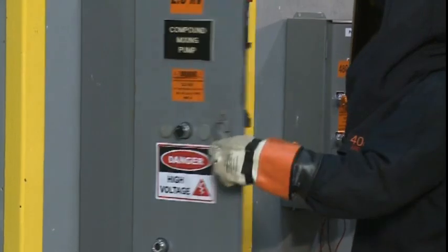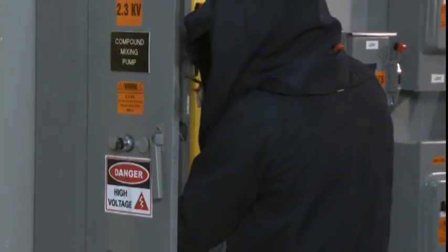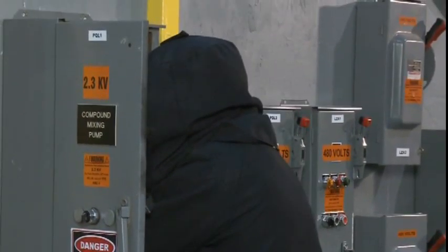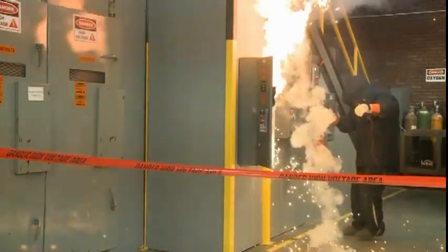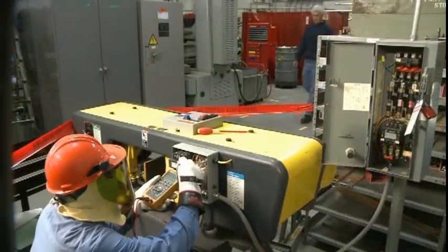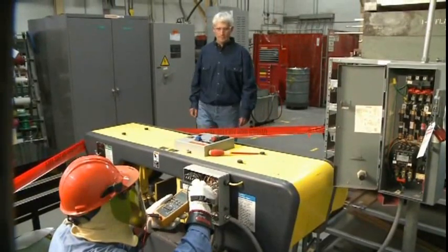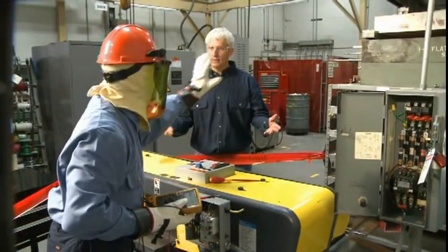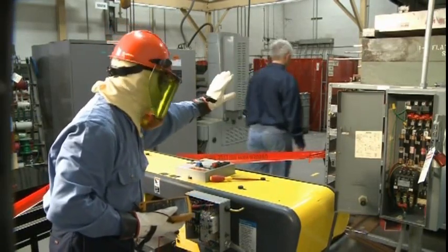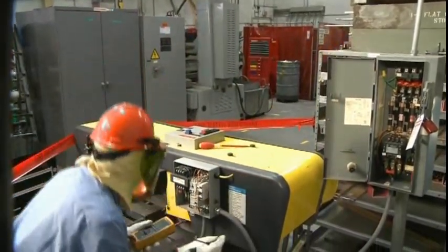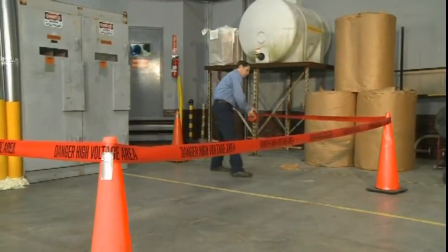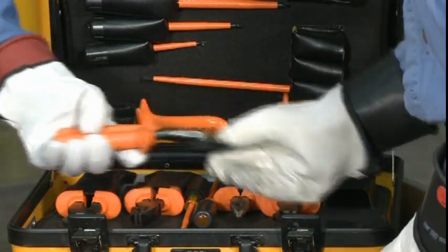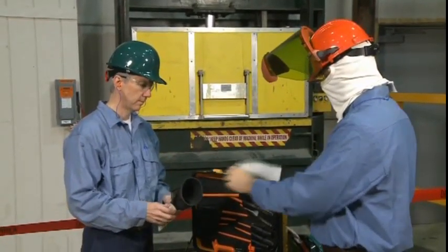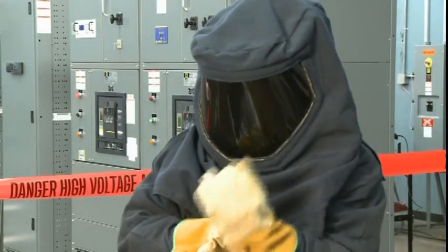Of course, make sure your meter is rated for the voltage and class of equipment you are testing. Exceeding a meter's rated voltage or class can lead to a serious incident. Remember that until you have verified the existence of an electrically safe working condition, the equipment must be considered energized. This means that all electrical safe work practices must be followed, including establishing approach boundaries, using appropriate insulated tools, as well as donning voltage-rated shock protection and appropriate arc flash protection.